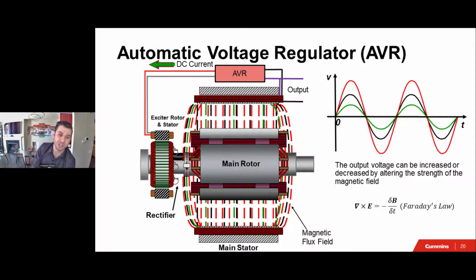On the other hand, from the generator, here is, for example, the rotor, here's the stator. We can change the output voltage. Let's say that we want to go from 480 to 490, or from 490 down to 460. What we do is we just invoke Faraday's law. We change that DC field where the rotor is spinning, that's cutting those field lines, and I can get higher voltage. Or if I want to go down to a lower voltage, all I need to do is decrease that DC field, and then that output voltage goes lower.